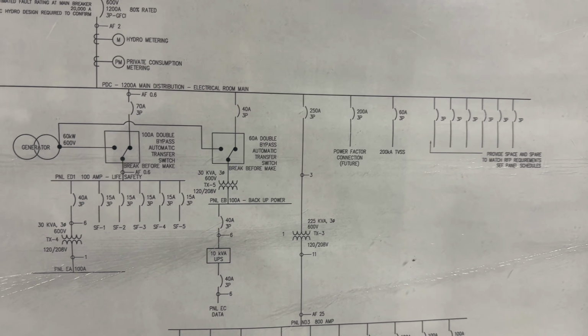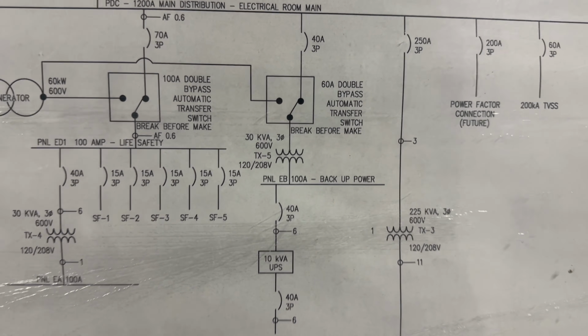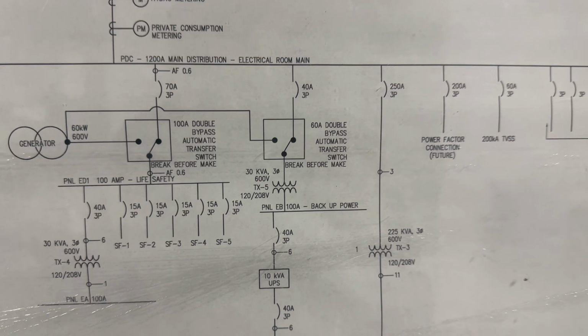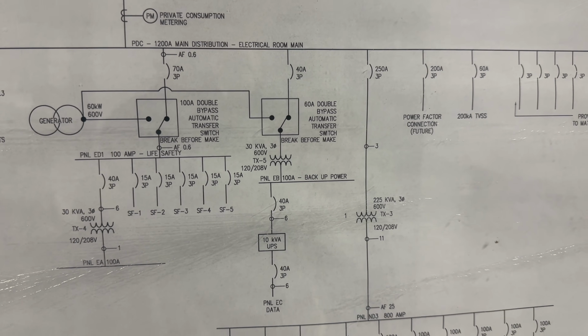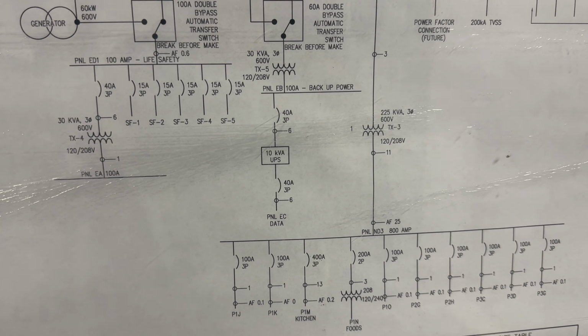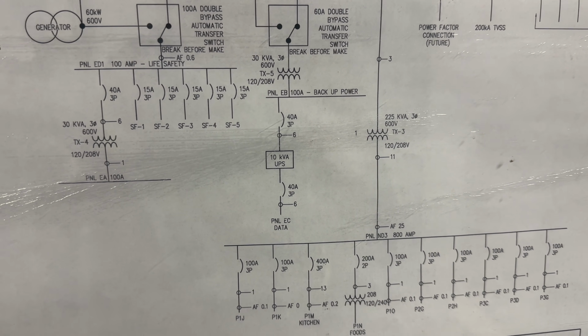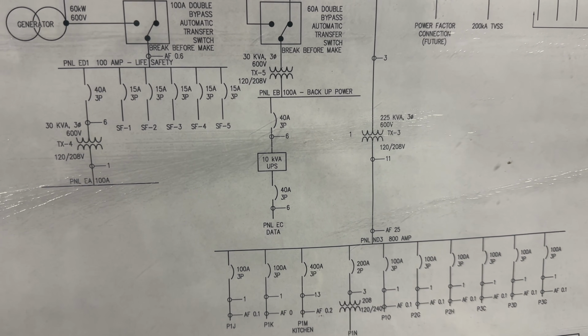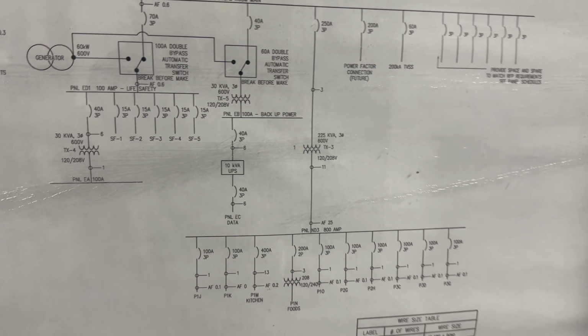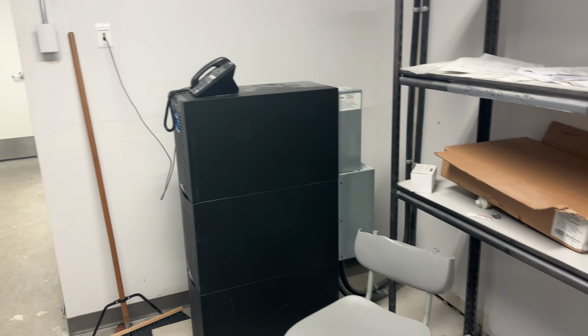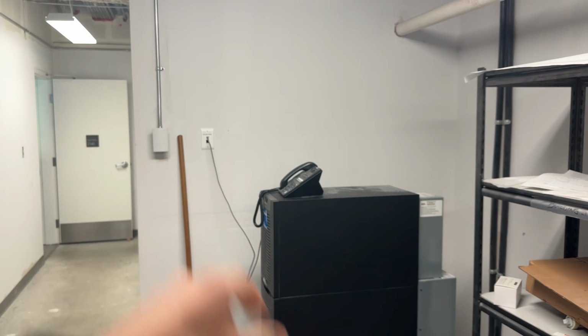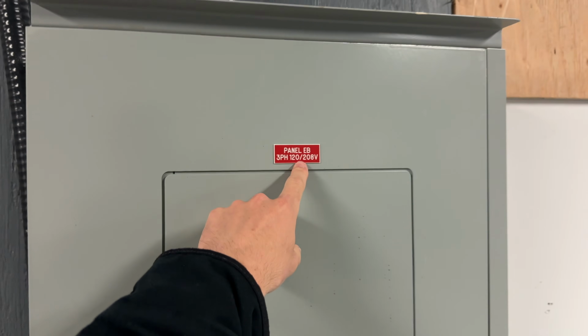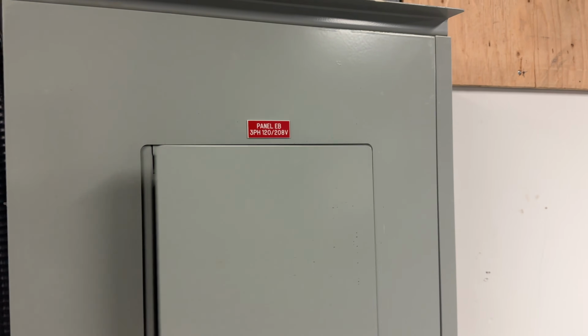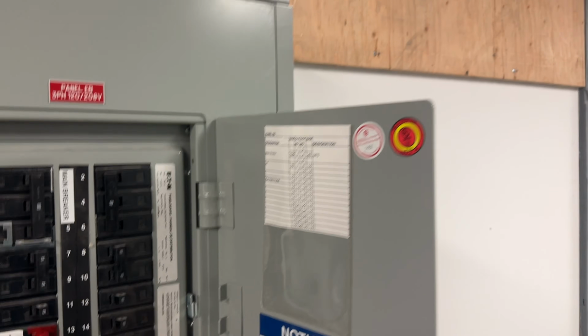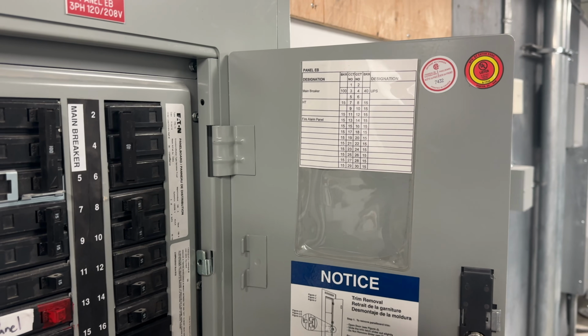And then on our standby side, we are going again through a transformer, taking us down to 120/208, another 30 kVA, and then we are going into a 10 kVA UPS, which gives us 40 amps out, and that's doing the data panel. So that panel provides everything data. So that UPS is right here. That's doing the data room over there. If the panel has a red Lamacoid label, that means it's emergency power. You can see this one here is one of the emergency panels.